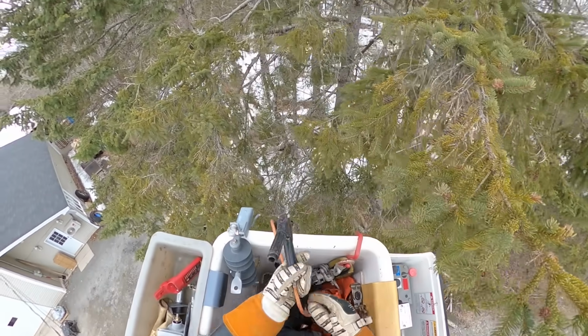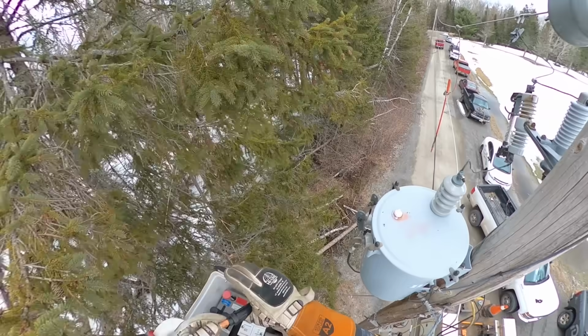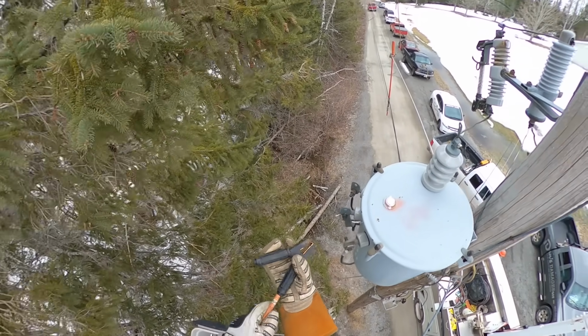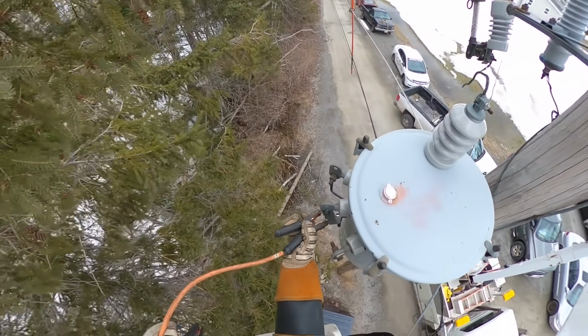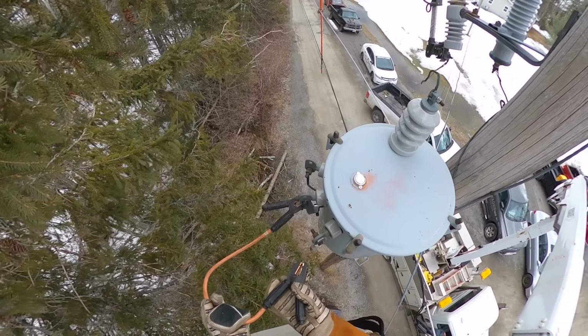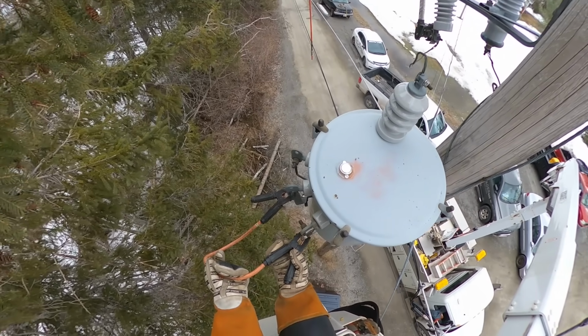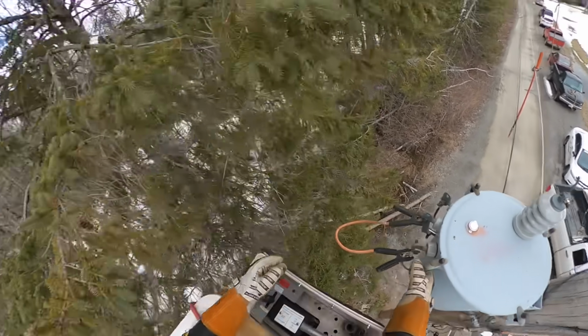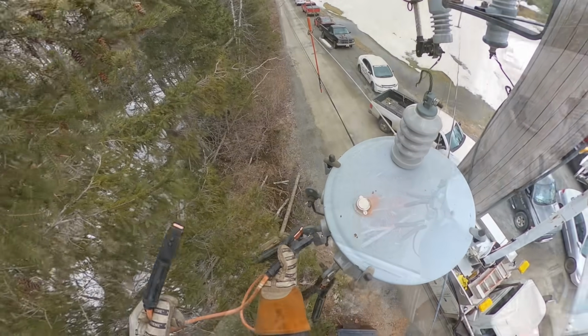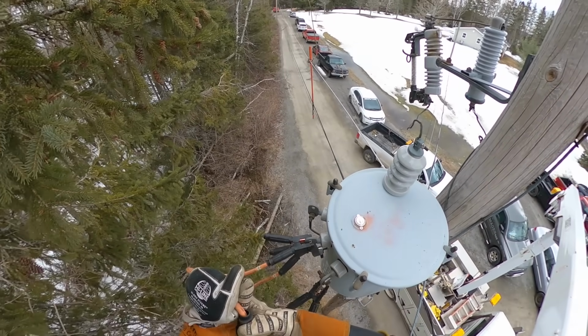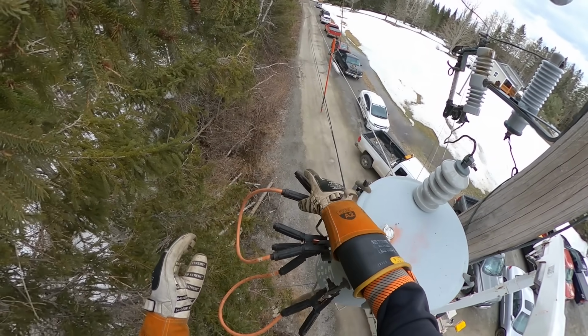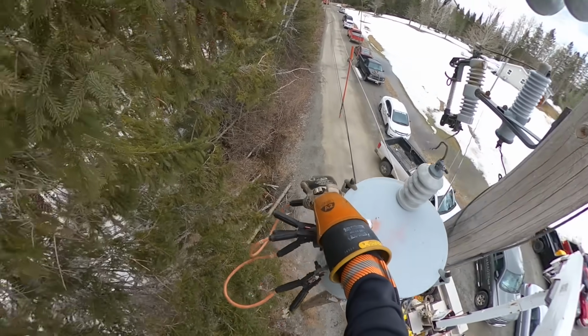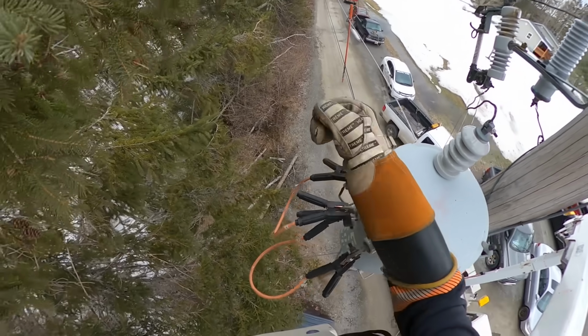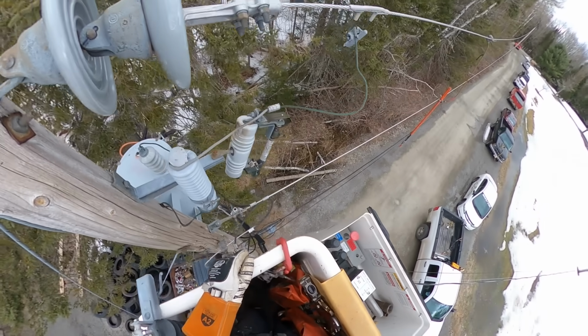So there's a few ways we could do this. You can hear a generator in the background. So if that generator is not hooked up properly, that could feed back up through that transformer, step that voltage up to 7,200 volts, and yeah, it'd be pretty dangerous. So we're basically shorting out the secondary lugs of the transformer. A few other options are to remove the leads from the transformer or remove the meter.